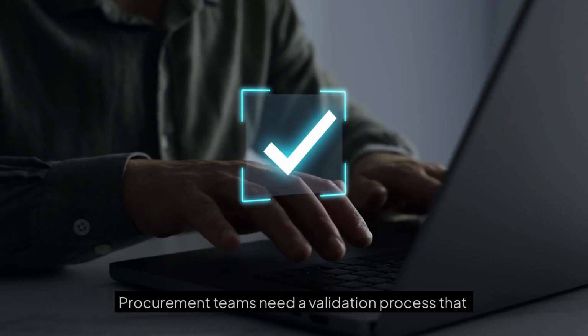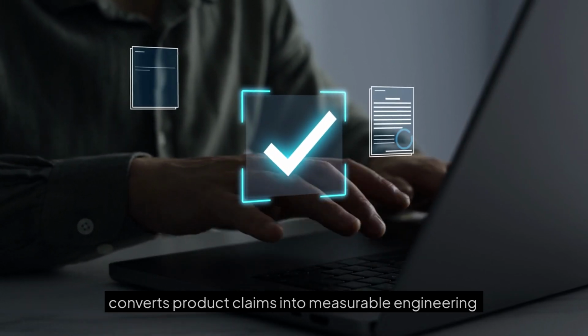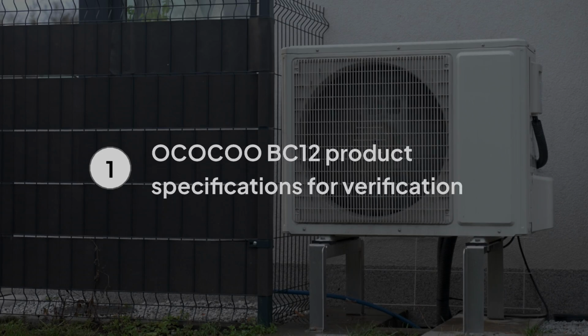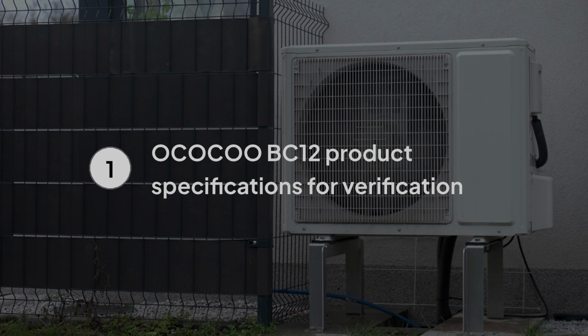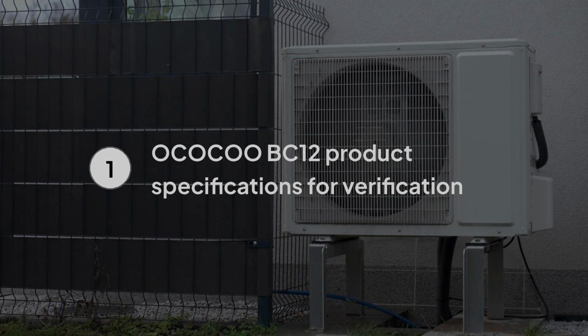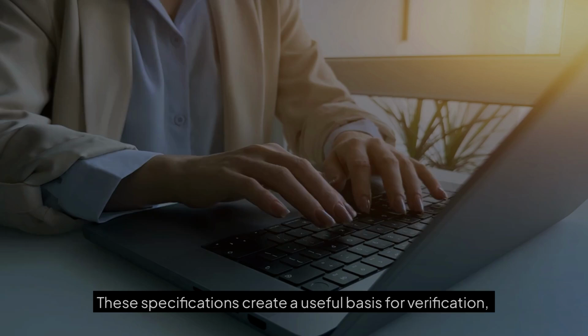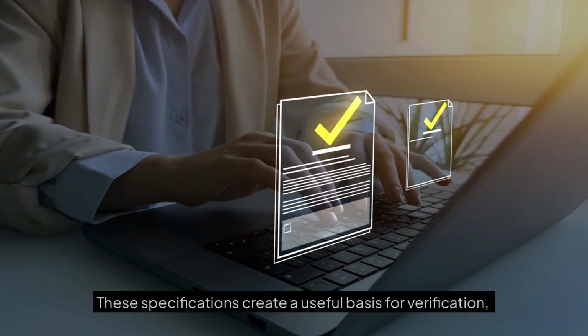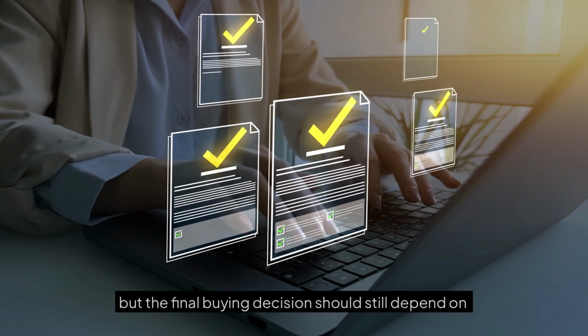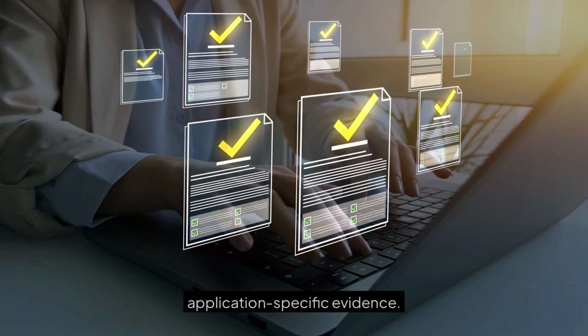Procurement teams need a validation process that converts product claims into measurable engineering questions. OCOCOO BC12 is used in this article as a practical example because the product page lists 12,000 W rated heat dissipation, 17 plus or minus 1 liter per minute maximum pump flow, 11 plus or minus 0.5 m pump head, 15 fans, 40 waterways, pure aluminum construction, and G1/4 threaded interfaces. These specifications create a useful basis for verification, but the final buying decision should still depend on application-specific evidence.